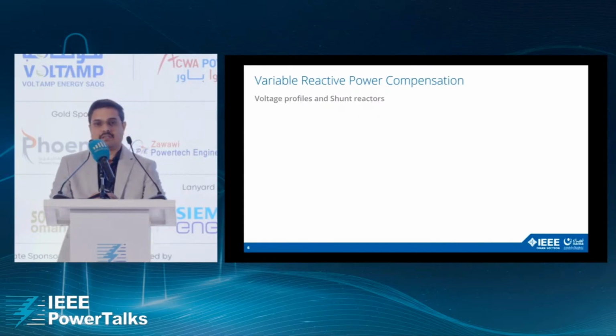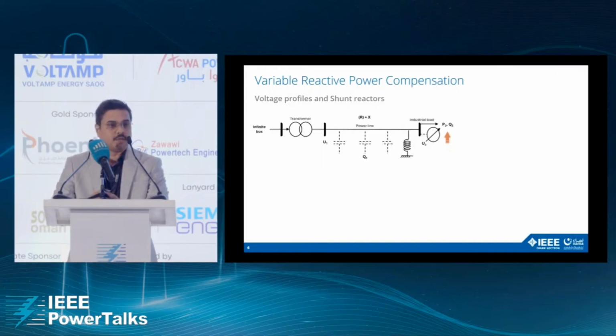But when we talk about actual scenarios in a power network, the requirement of different industrial customers is not constant. It keeps on varying with the different loads. Consider a situation where you have the shunt reactor connected to a system and the load, and the demand for reactive power by the industrial customers also increases. In this scenario, what will happen? The shunt reactor is overcompensating the network, so the total reactive power generated in the system is less, whereas the total demand by the industrial customer plus the shunt reactor is more. So you will have less voltage at the consumer level, which will make the equipment there not work at a satisfactory level, because it's not getting the total voltage it requires.